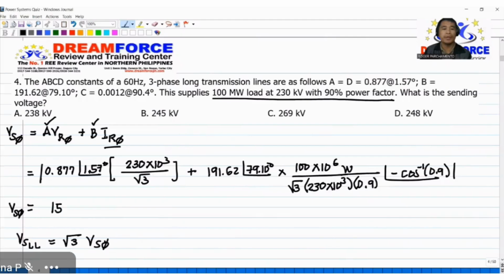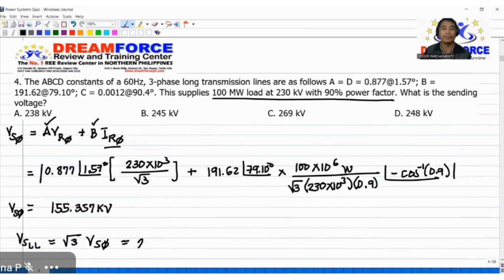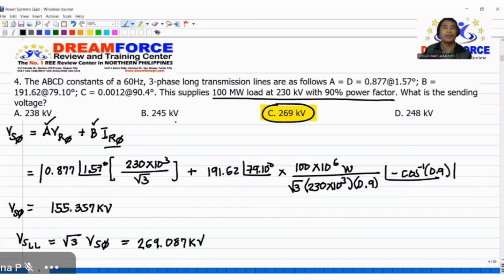155.357. So 155.357 kilovolts. So multiplied by square root of 3, multiply this value by square root of 3. So 269.087. So letter C is the answer to number 4. The other variables or constants are used in solving for IS per phase. That is C times VR per phase, then plus D times IR per phase. So they are all in vector quantities.